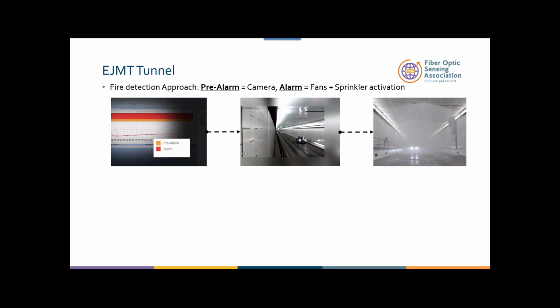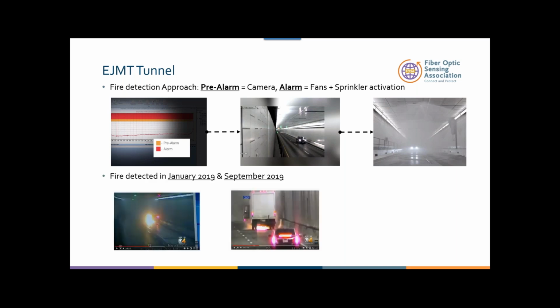When we do these tests, and then try the system every year to make sure that the system is responding, these are the pictures we get all the time. Unfortunately, when we install fiber optic linear detection for fire detection, we certainly don't want to have fires. It's just not good for anybody, but we do it for one reason. Number one, it could be a code. We have to do a fire detection system anyway. Number two, we really want to save lives and make sure that people are in a very, very good situation.